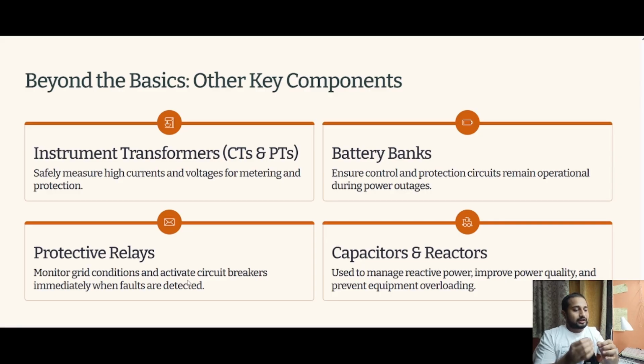If the current measured by the current transformer exceeds the permissible value, then the protective relays send a signal to the breakers, and they immediately isolate the equipment in order to protect it from the fault. Then the next important equipment is battery bank. They ensure control and protection circuits remain operational during the power outages. If there is any power outage in a substation, then the battery banks act as a backup to ensure the protection equipment runs safely.